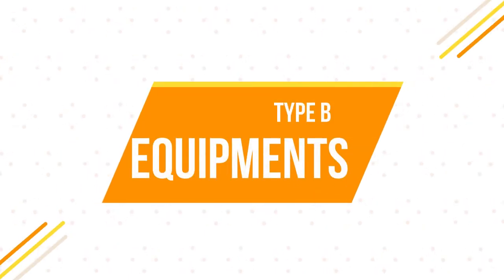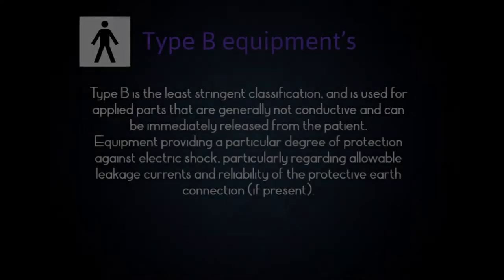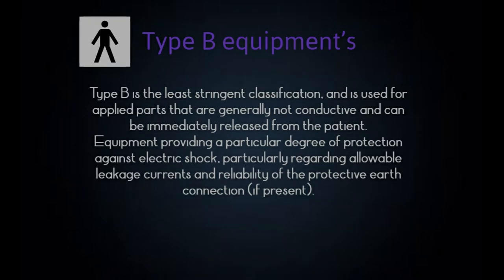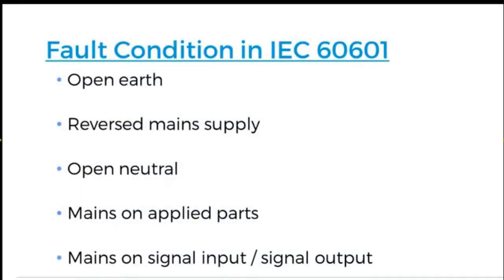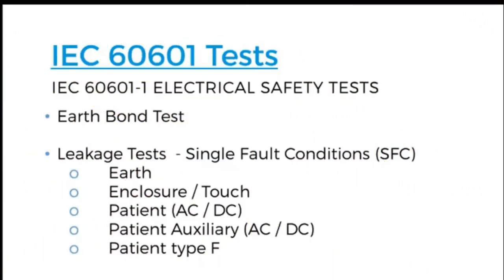Let's begin with Type B Equipment. Type B is the least stringent classification, and is used for applied parts that are generally not conductive and can be immediately released from the patient. It provides a particular degree of protection against electric shock, particularly regarding allowable leakage currents and reliability of the protective earth connection, if present.